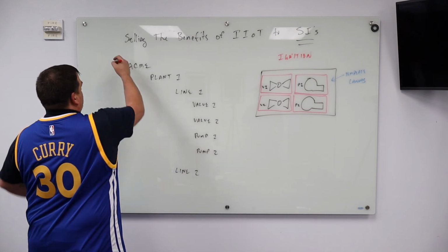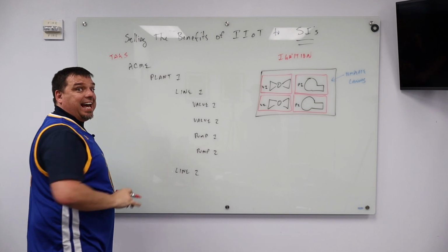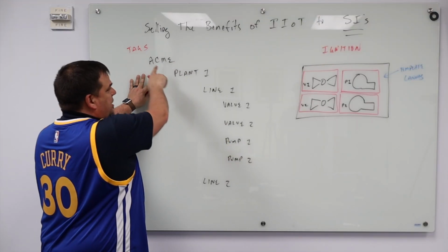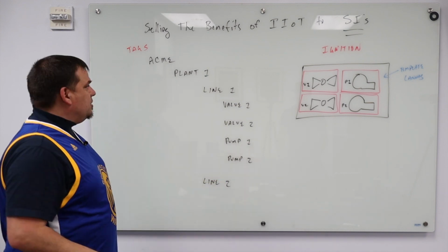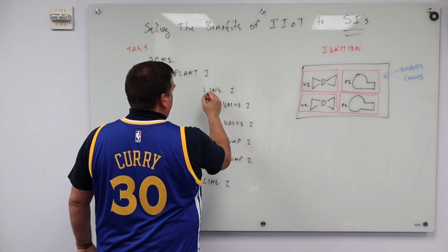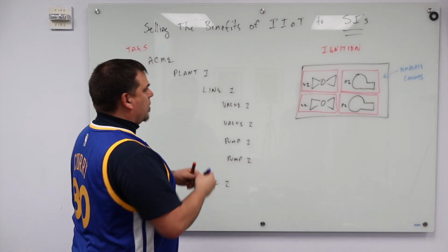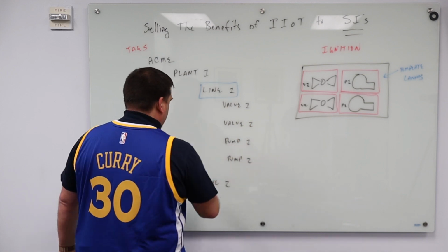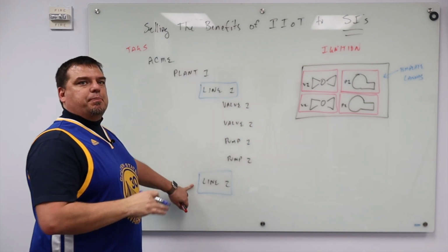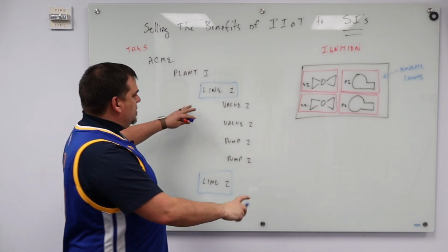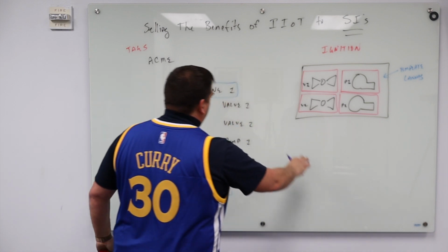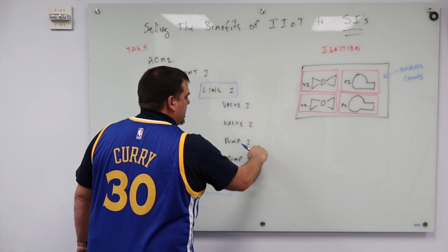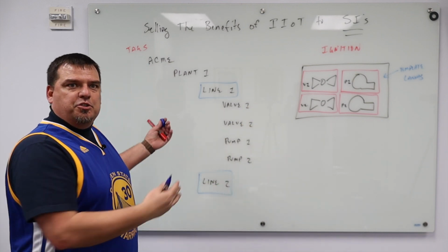So this is my tag structure inside of Ignition. These are my tags. Now, using Sparkplug B from our PLCs, we can generate these tags using MQTT. So I can bring on new lines, I can bring on line 1. Our screen lines up with the line. We basically built a line screen, and I'm going to explain what that means in a minute. But these boxes also line up with our PLCs. So once our PLC publishes into the namespace, this is the client ID. Line 1 is going to show all of the objects that live inside that PLC using MQTT.